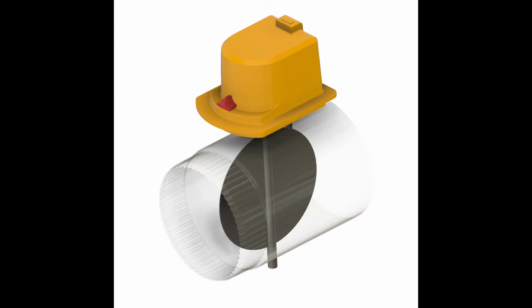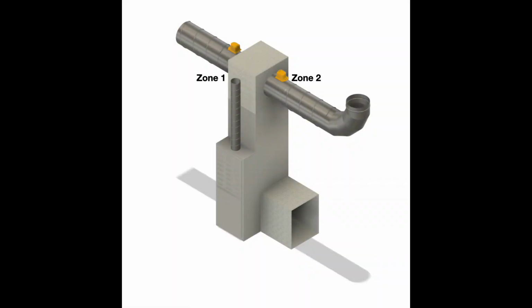The purpose of zone dampers is to better control the airflow through an HVAC system in hopes to help it operate more efficiently and increase occupant comfort. So here's an example of a two-zone damper system. You can see zone 1 here is supplying air to the first floor in the building. Zone 2 is supplying air to the second floor in this building. The return air comes in here in the return plenum, goes up through the furnace and your evaporator coil into your supply plenum. And those two zone actuators will open or close depending on how you program the controller.